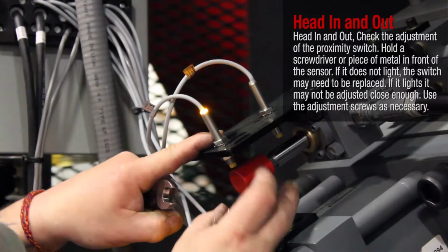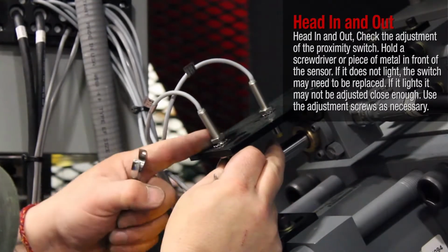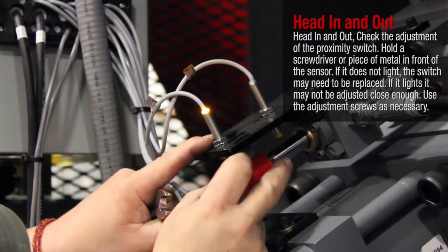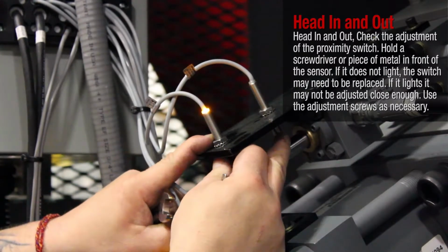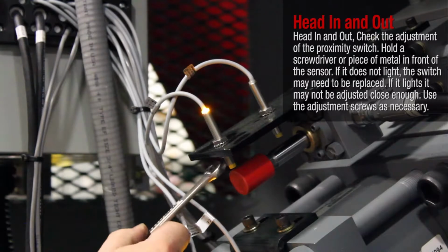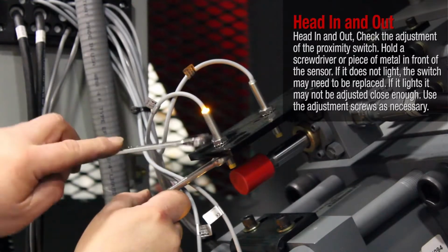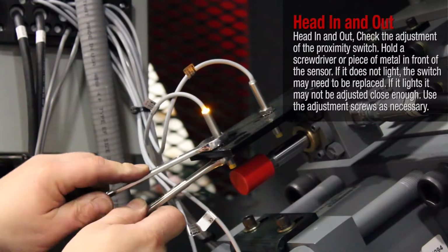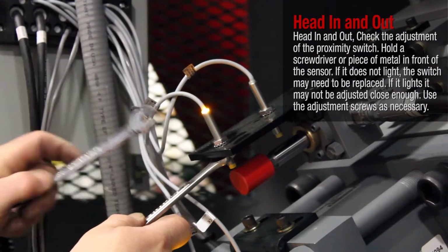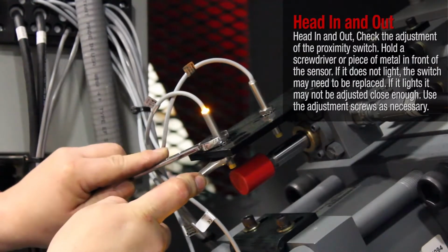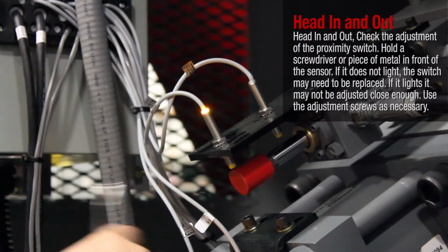Head in and out. Check the adjustment of the proximity switch. Hold a screwdriver or piece of metal in front of the sensor. If it does not light, the switch may need to be replaced. If it lights, it may not be adjusted close enough. Use the adjustment screws as necessary.